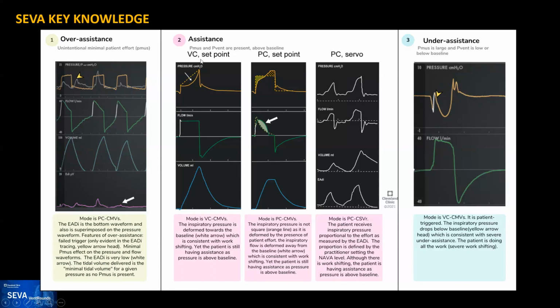And so here you have an example in volume control, and you can see that even though the pressure gets deformed in the presence of PMUS and muscle effort, it's still above the baseline, which means that the ventilator is delivering more flow than the patient needs, which means that the patient is being assisted. The same here you see in pressure control. There's evidence of PMUS on the flow waveform, and you can see that the pressure is above the baseline. And although it deforms somewhat as a manifestation of the PMUS, the pressure is above, so there's assistance.